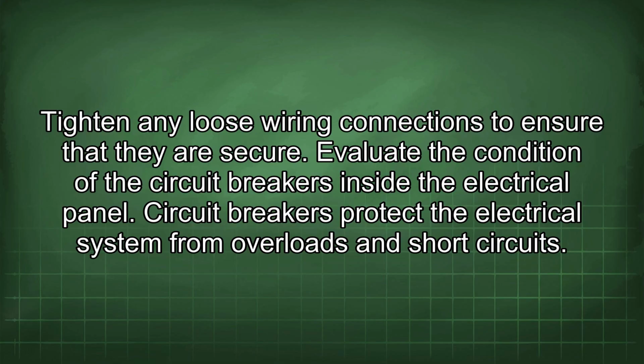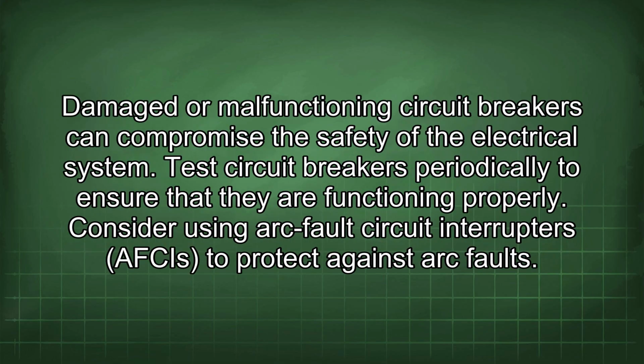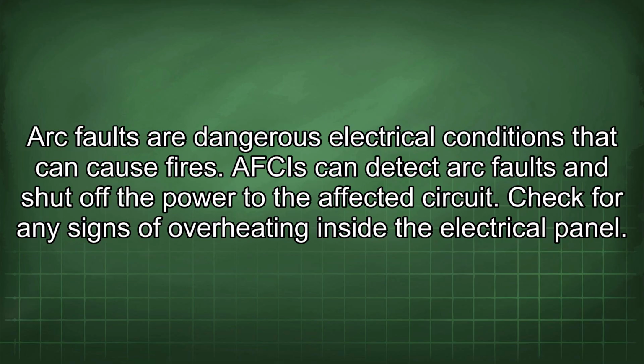Evaluate the condition of the circuit breakers inside the electrical panel. Circuit breakers protect the electrical system from overloads and short circuits. Damaged or malfunctioning circuit breakers can compromise the safety of the electrical system. Test circuit breakers periodically to ensure that they are functioning properly. Consider using arc fault circuit interrupters, or AFCIs, to protect against arc faults. Arc faults are dangerous electrical conditions that can cause fires. An AFCI can detect arc faults and shut off the power to the affected circuit.